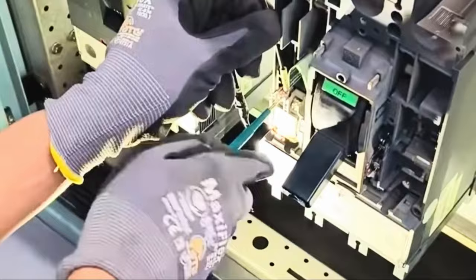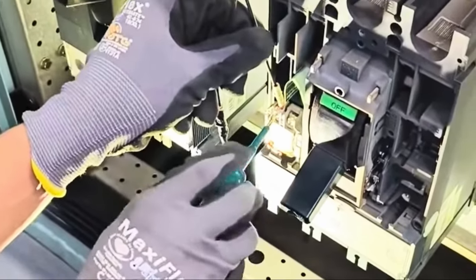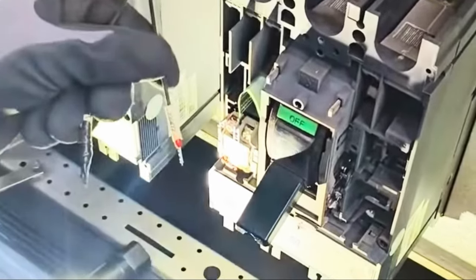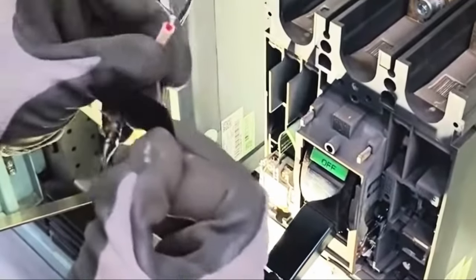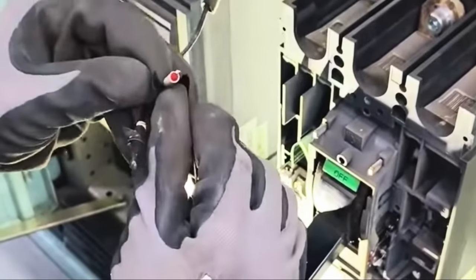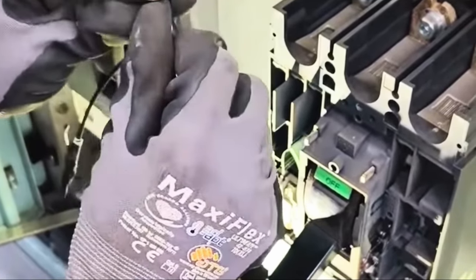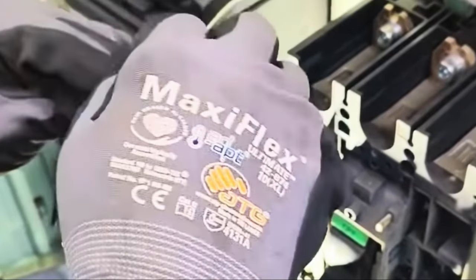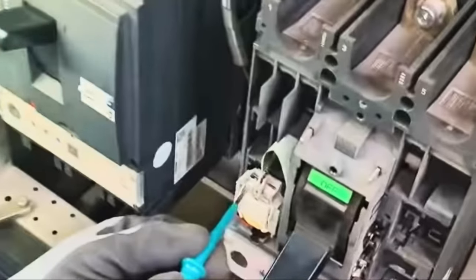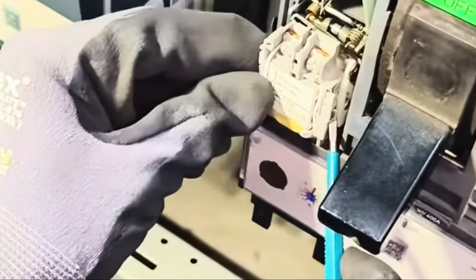Before removing the connection, you should ensure that it is properly isolated. The LOTO procedure must be strictly followed, and safety gloves, safety shoes, and everything must be properly worn, because it also has 440 volt AC, as per the design of the UVR, whatever voltage is available as per the controlling of the MCCB. In our case, we have 440 volt on the terminal of the under voltage relay. We checked with the multimeter: the under voltage relay has 440 volt, so there is no connection problem.